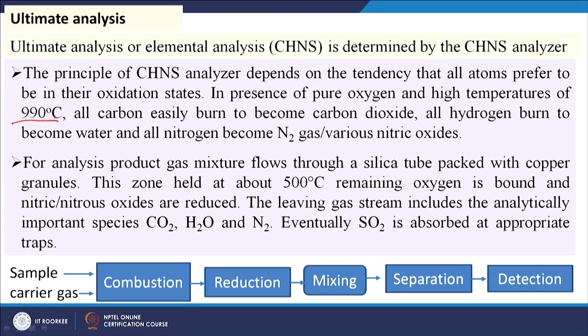What is the mechanism for this analysis? The coal sample is combusted at a higher temperature — specifically 990°C. When heated, carbon is converted to CO₂, H to H₂O, N to NOₓ, and S to SOₓ. We get a mixture of gas components. The material is put in a small container, oxygen is applied and it is heated, and then the gas is available in the container. A carrier gas carries and mixes the components, and gas chromatography is used for separation and identification of the gas molecules.